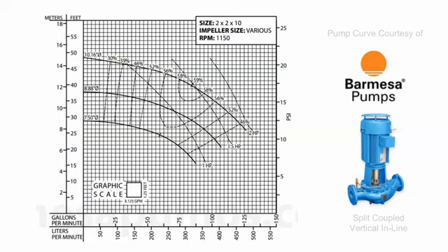In some cases, it can be a challenge to operate extremely efficiently, or to find a pump whose curve matches your application to a T. So the generalized rule of thumb is you go to the center point, and then you can go roughly 30% of the curve in either direction, and that's going to be your recommended operating zone. So you've got the best efficiency point here where the highest efficiency is achieved, and then when you take roughly 30% of the curve in either direction and draw an imaginary line, then that's going to be your recommended operating range. And I would avoid operating outside of the recommended operating range on most pumps.